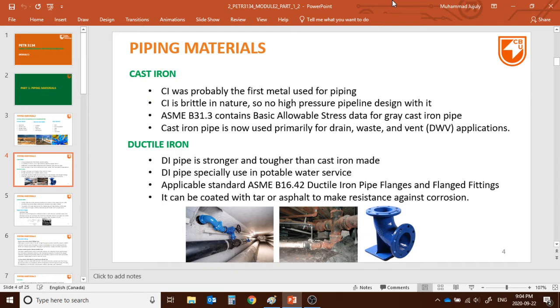We still use cast iron pipe sometimes because it's cheap — primarily for drainage and wastewater vent types of use. Ductile iron is stronger than cast iron and is usually used in potable water services. Probably you have seen these types of piping works — those are actually ductile iron. ASME B16.42 covers ductile iron pipeline flanges and flange fittings — that's the standard we follow for ductile iron pipeline design. It can be coated with tar or asphalt to make it more resistant to corrosion.